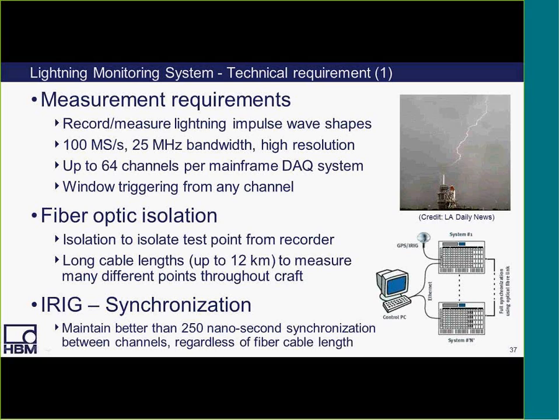So, in this lightning monitoring system, the technical requirements to meet the demands of this application included recording and measuring lightning impulse wave shapes at 100 million samples per second with 25 megahertz bandwidth and high resolution, capable of measuring up to at least 64 channels per mainframe in a data acquisition system, with window triggering from any channel. Now, the fiber optic isolation requirements included isolating the test point from the recorder, and long cable lengths up to 12 kilometers to measure many different points throughout the craft.